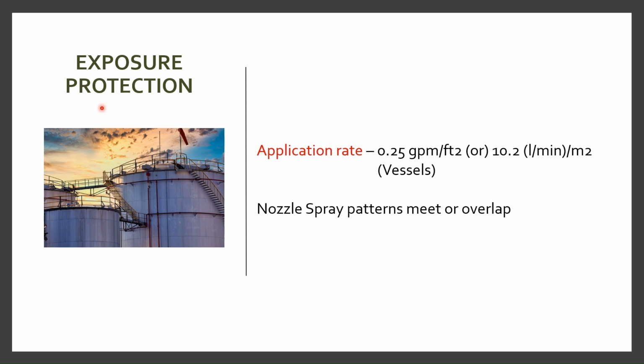Exposure protection. The water spray system shall operate as intended for the anticipated duration of exposure fires. Basically, exposure protection is applicable for vessels. The application rate would be 0.25 GPM per square feet as per NFPA 15. Nozzle spray patterns must meet or overlap. This is also a requirement for all the equipment while designing the water spray system. There are a few more considerations to be discussed. We will discuss those in detail when we consider a particular project of a water spray system protecting vessels, and this will be discussed in the next classes.